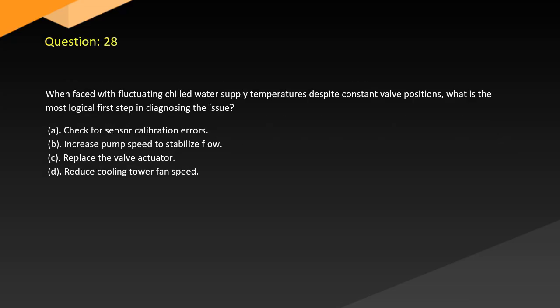Question 28. When faced with fluctuating chilled water supply temperatures despite constant valve positions, what is the most logical first step in diagnosing the issue? A. Check for sensor calibration errors. B. Increase pump speed to stabilize flow. C. Replace the valve actuator. D. Reduce cooling tower fan speed.